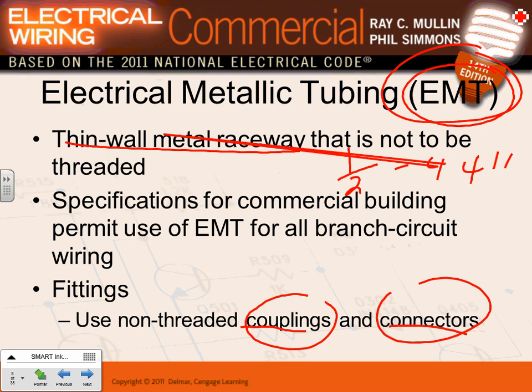Conduits are very simple: if you're above ground, your conduit of choice is EMT. If you're below ground, your conduit of choice is PVC. If you're pulling feeders, you almost have to put them in a conduit. If you have severe physical protection needs or a hazardous location, your conduit of choice will be rigid metal conduit. That's as simple as it gets in terms of conduit selection.